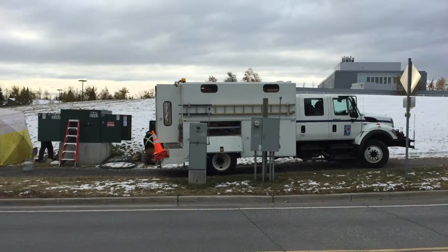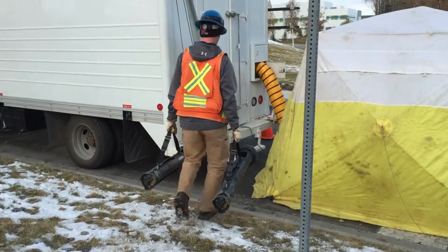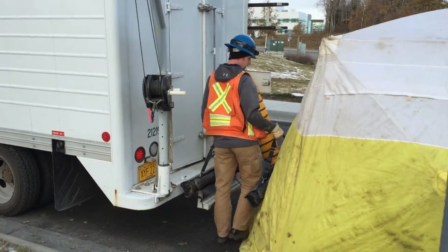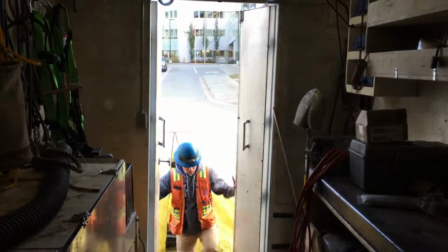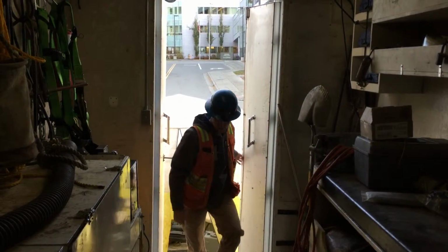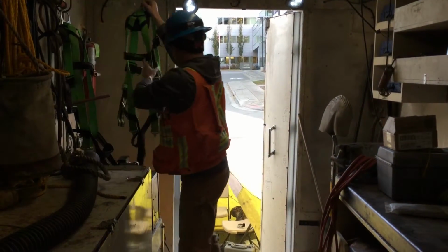Although we've done this dozens of times, we're always improving our methods and techniques. There are many obstacles to modeling these underground vaults. It is not a casual endeavor. This includes blocking off traffic to access our manholes and roads, scheduling 3 to 6 men from our operations department, sometimes deploying a vacuum truck to remove water if the vaults are full. We are continually monitoring the atmospheric conditions inside the vault.